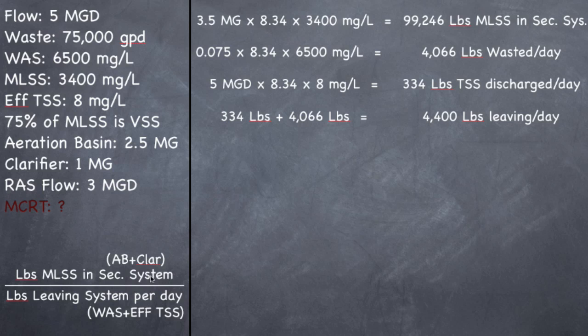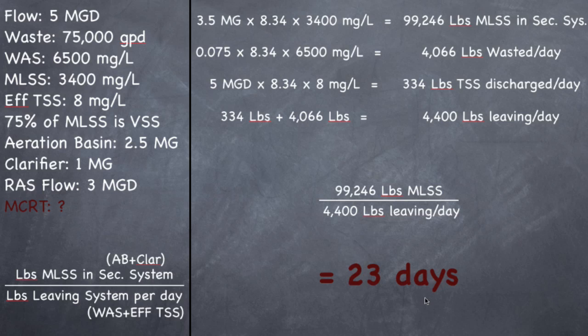Now we have the top part and the bottom part. Let's put them all together. 99,246 pounds of MLSS in your secondary system divided by 4,400 pounds leaving per day should give you an MCRT of 23 days.